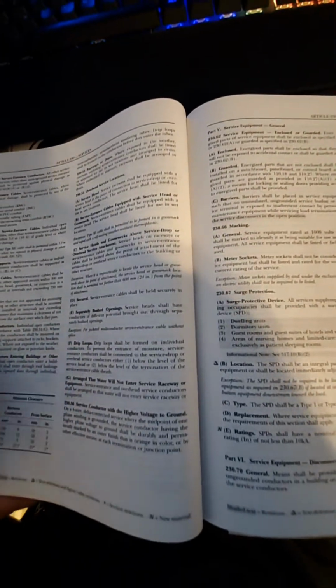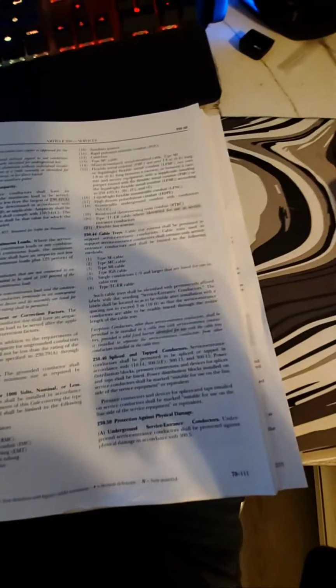Service entrance cables, open conductors of cables other than service shall be installed 10 feet above grade. Nope, that's the 3 meters. Sometimes it's harder when you know the answer, and then you're kind of just looking all around for it. There's barriers, there's guarded, enclosed. There's location. Let's go back 1 here, because that index is just going to get us close. We're looking for the clearances.